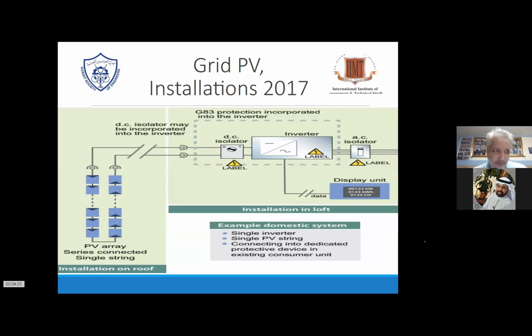So usually it's between 3 and 5 volt higher than the existing. And the more inverters you've got, the higher it gets. So you can measure up to 250, 255 I had in some installations. So it actually lifts the voltage of the individual house to a higher voltage. So each individual plug has then up to 250 volt, which also causes problems because the inverter will always feed to the maximum availability, and he will always search for the transformer, although more or less you use it on site.